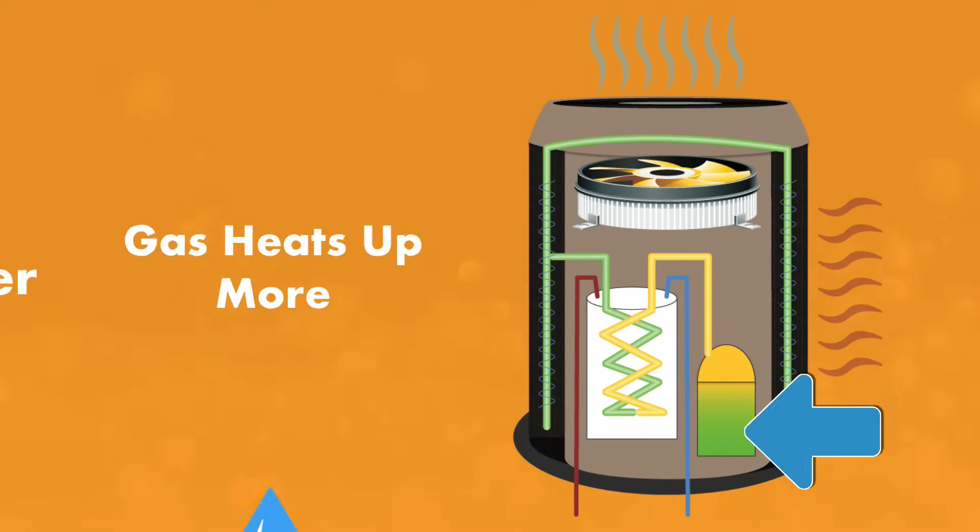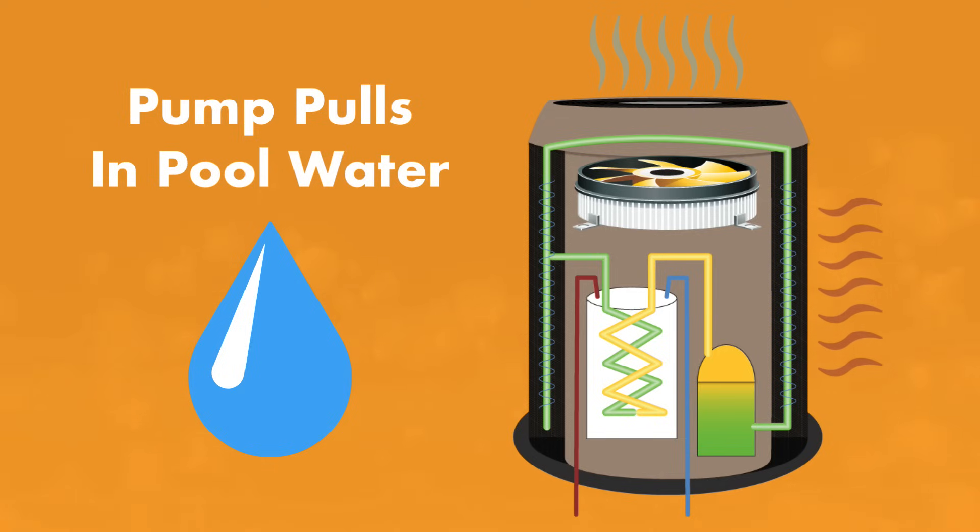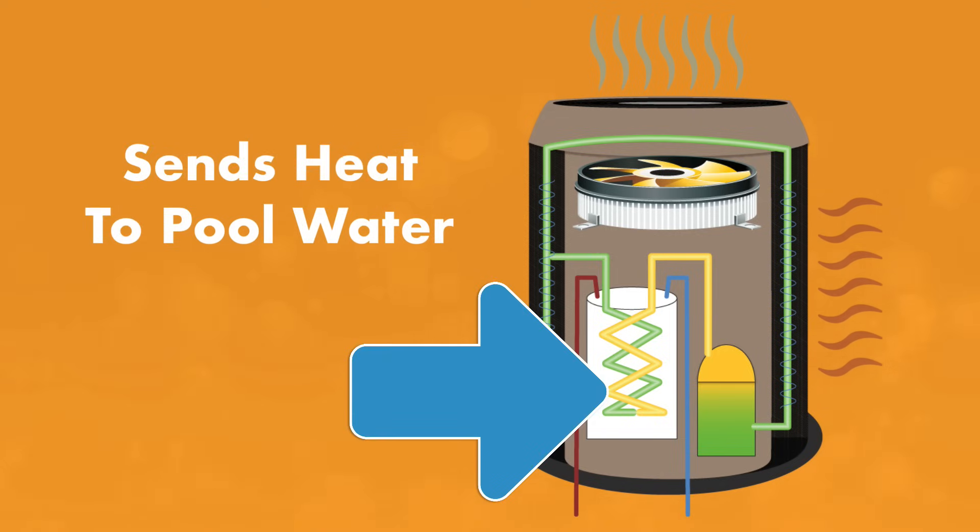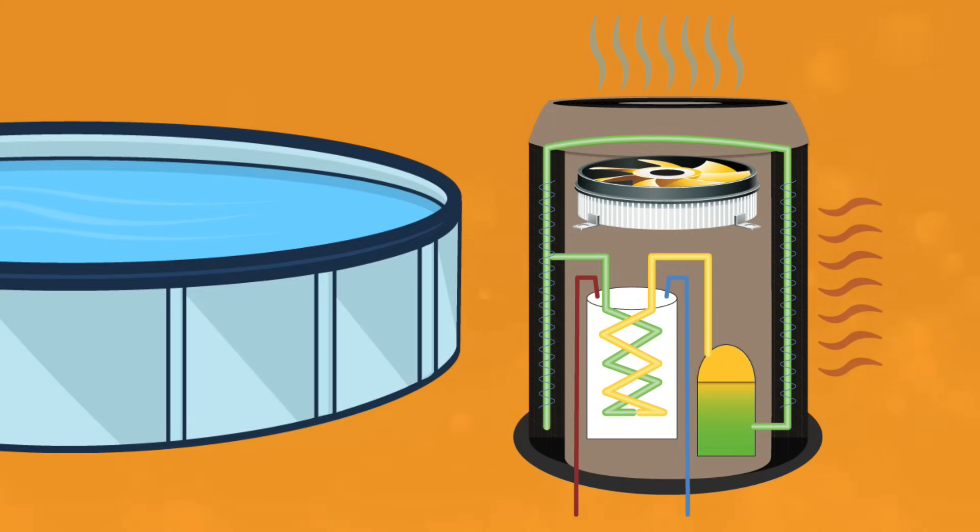At the same time, your pump is pulling in cooler pool water. The hot gas and the cool water transfer heat in the heat exchanger, warming up your pool water by three to five degrees Fahrenheit. Then that warmer water flows back into your pool. Meanwhile, the hot gas is passing through your condenser, turning back into liquid freon, and the entire process begins all over again.